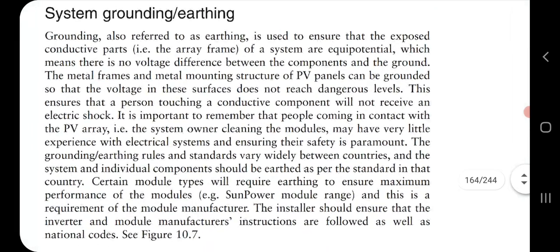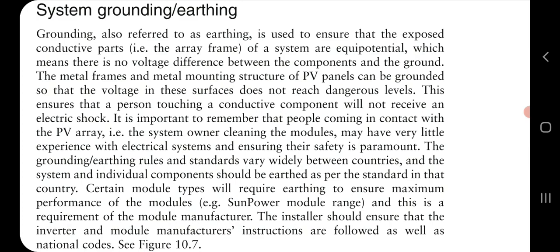Now, earthing and system earthing, grounding and earthing. When we are installing a PV system, there are many supporting or mounting structures made of metal. When any current flows through that metal, the voltage will be very high, and a person who touches it will get a shock. So the paramount concern is safety, which has to be provided to each person working on the PV system. For this, they do grounding or earthing. All the components, structures, and the metal frame and metal mounting structure of the PV panel are grounded, so that they are at equipotential.